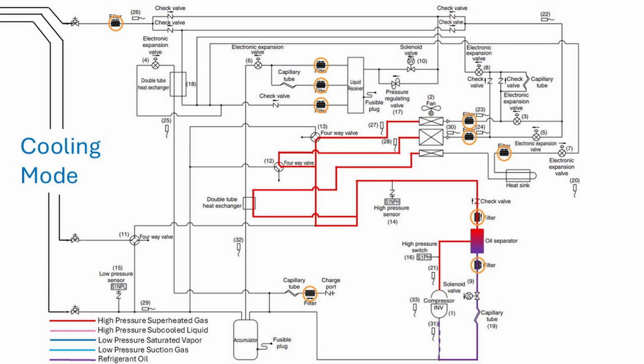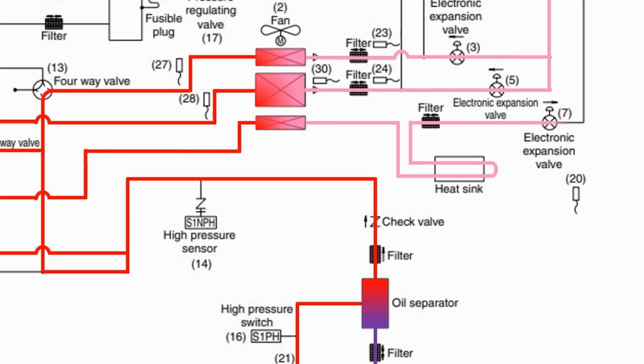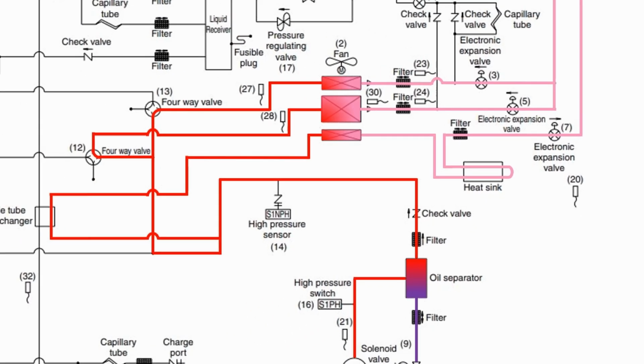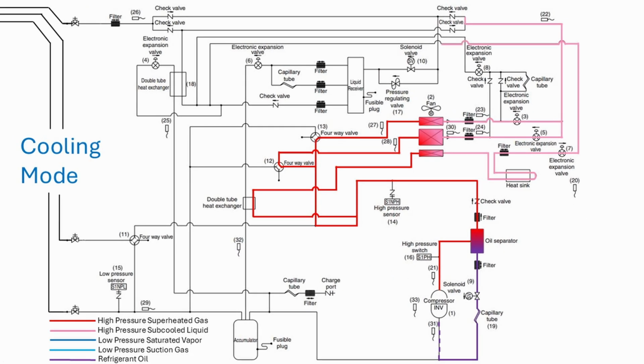You will notice the presence of several refrigerant filters in this system, making a clean refrigerant piping installation even more important. As the refrigerant passes through the outdoor heat exchanger, it is subcooled into a liquid. The smallest section of this heat exchanger, which is the bottom in this case, first passes through a heat sink to cool the inverter section of the control board. As the liquid refrigerant leaves the outdoor heat exchangers, it passes through electronic expansion valves. Since this system is in 100% cooling mode, all of these valves are pulsed wide open and not metering.